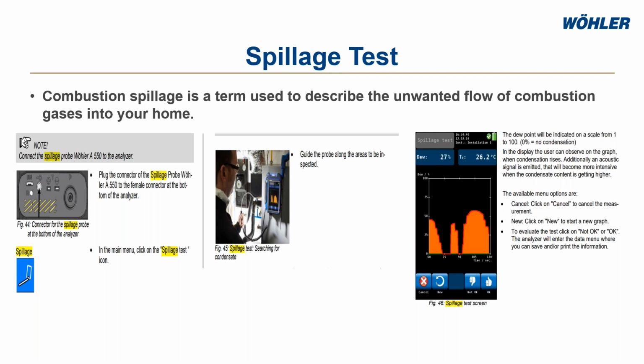It's really simple to use. You would go into your main menu and select spillage test. It's going to bring up the graph that you see all the way to the right, and it's going to start detecting with the probe attached. It's going to tell you if there's any flue gas spillage, and it's calculating using the dew point. Then you can put these test results in your report, or obviously you can leave them out.